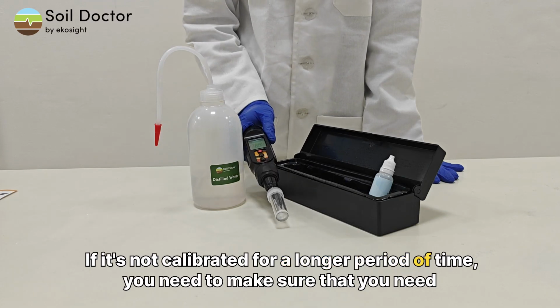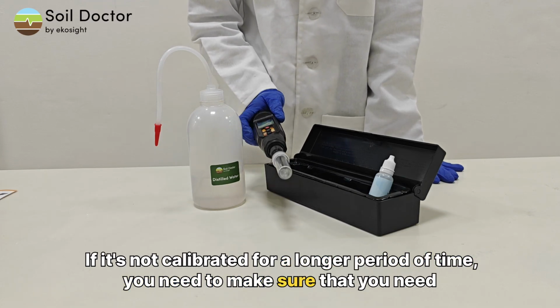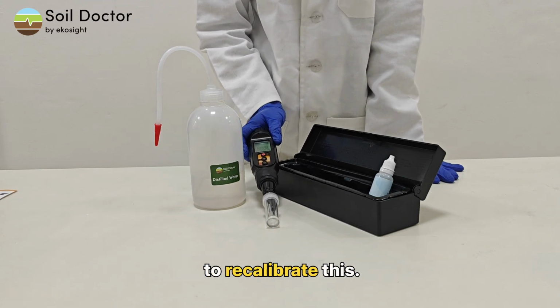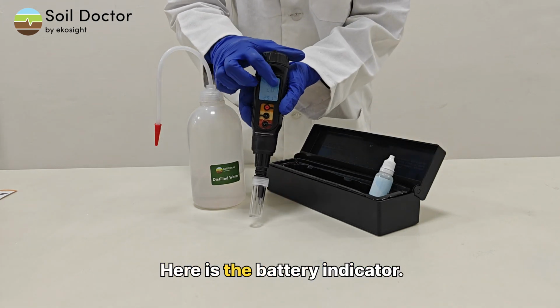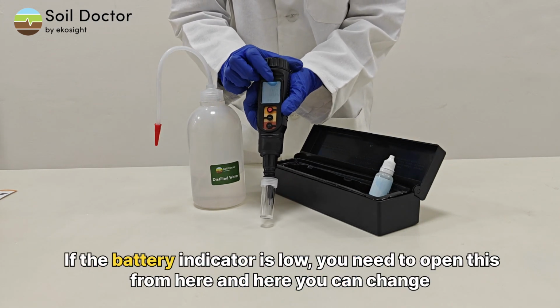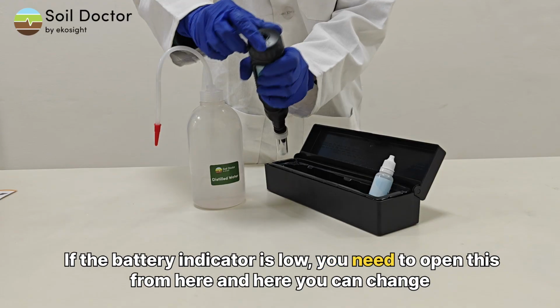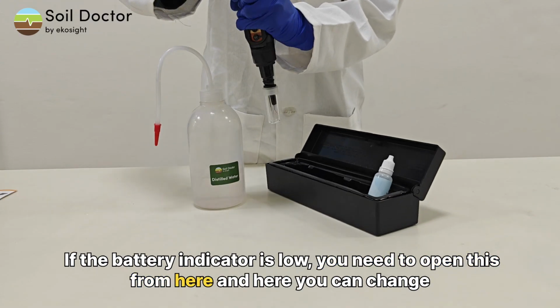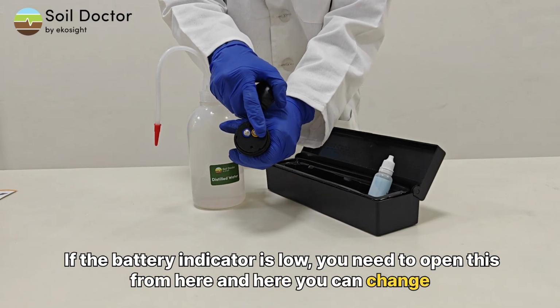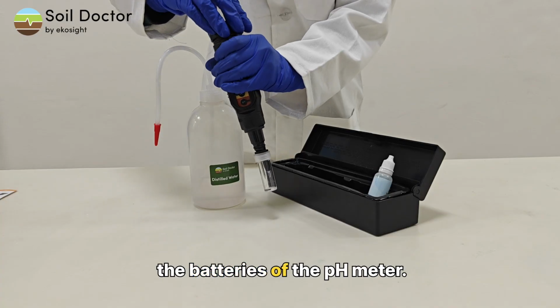If it's not calibrated for a longer period of time, you need to make sure that you recalibrate this. For battery, here is the battery indicator. If the battery indicator is low, you need to open this from here, and here you can change the batteries of the pH meter.